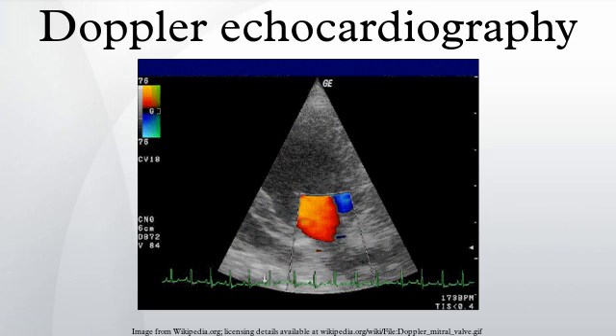Comparing vector Doppler and speckle tracking: both methods could be used for 2D velocity vector imaging, but speckle tracking would be easier to extend to 3D. Also, in vector Doppler, the depth and resolution of the region of interest are limited by the aperture size and the maximum angle between the transmit and receive apertures, while speckle tracking has the flexibility of altering the size of the kernel and search region to adapt to different resolution requirements. However, vector Doppler is less computationally complex than speckle tracking.